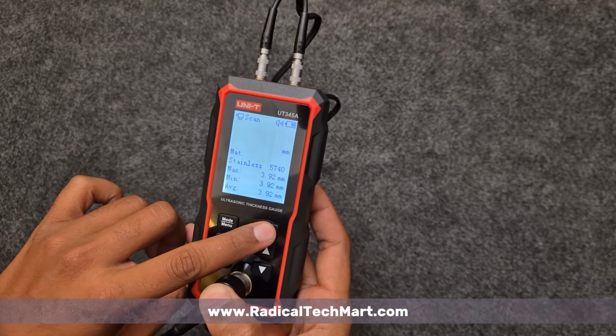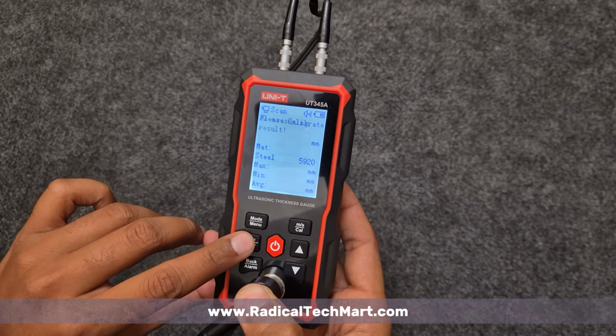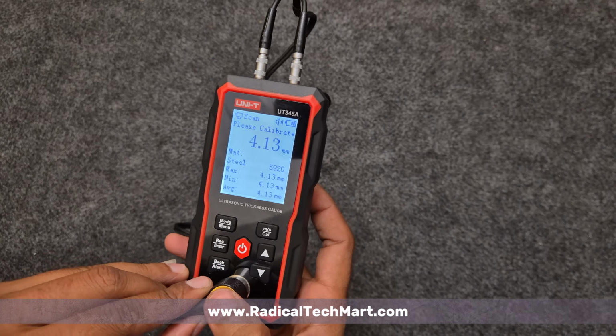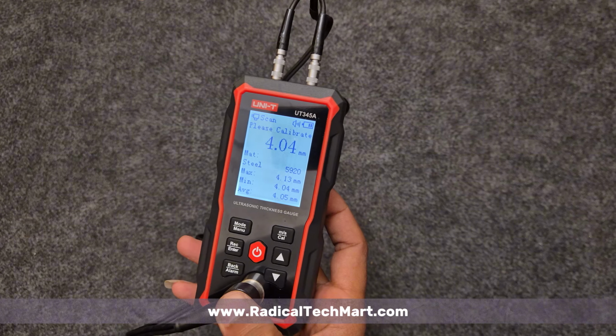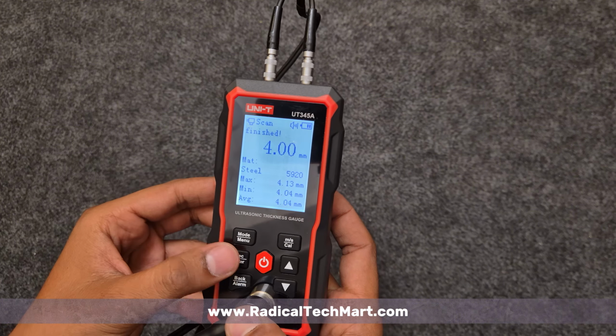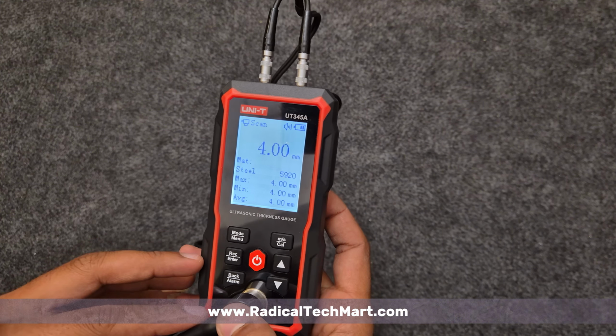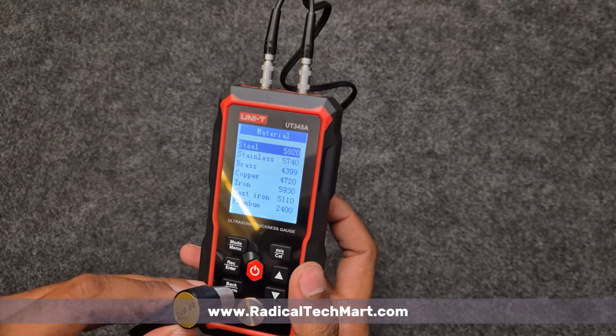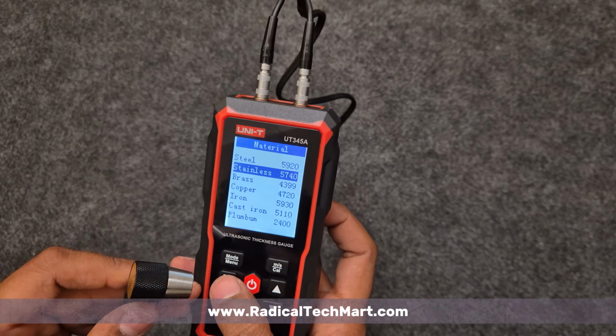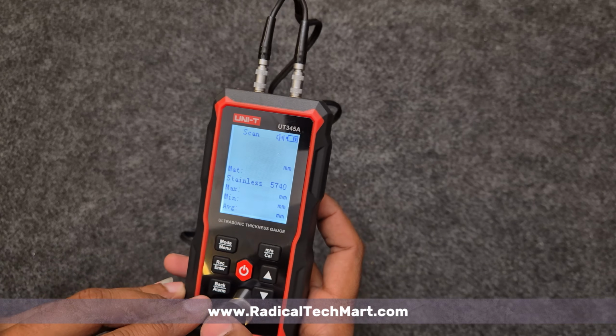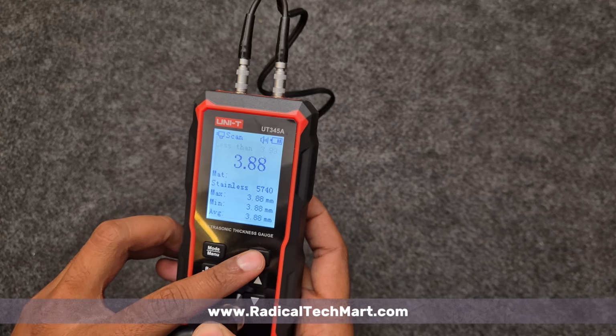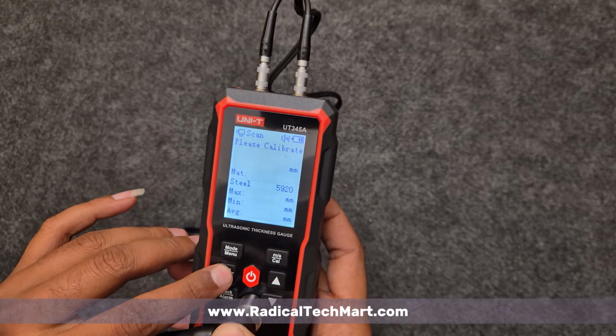Calibration. Before using, always calibrate. Just place the probe on the included 4 mm standard block. The device auto-adjusts to 5920 meters per second, the velocity of steel. You can also set custom velocities for other materials. This ensures accurate, reliable readings in the field.